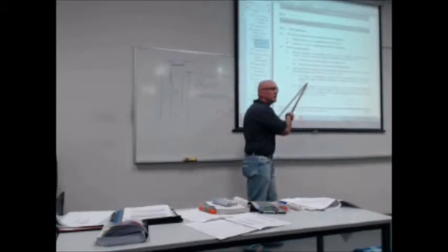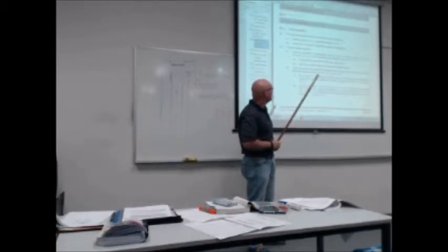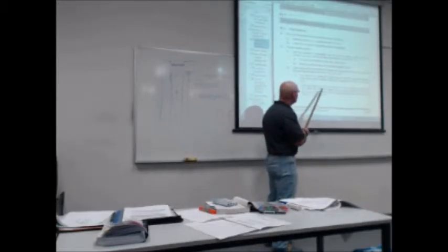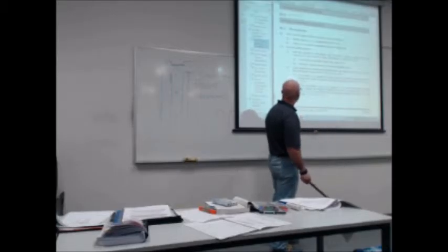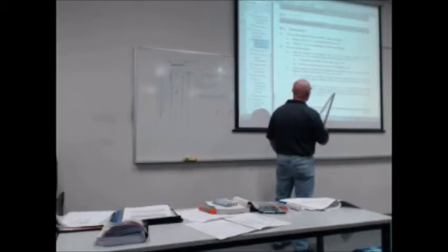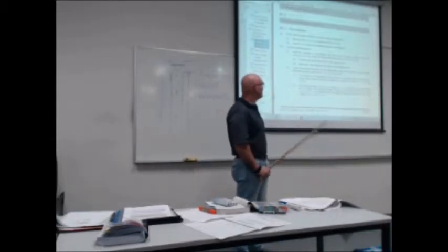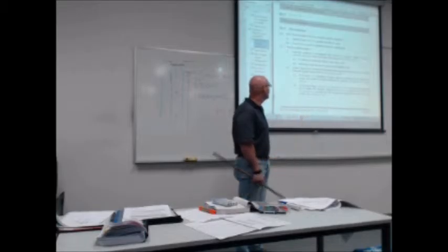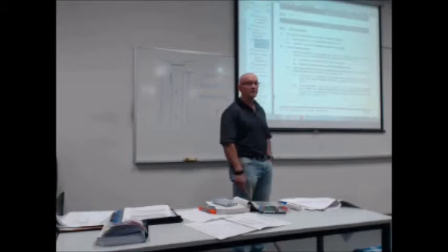And not more than two storeys, which is what this is. A single one, so we only need one, located at the level of egress from that sole occupancy unit, provided the fire hydrant can provide coverage to the whole of the sole occupancy unit. So one inside the front door.